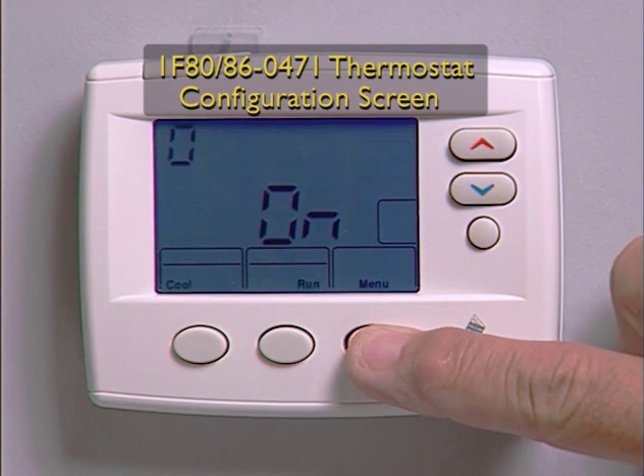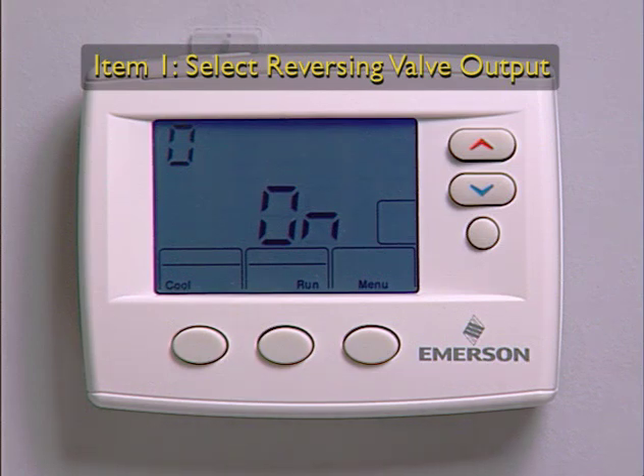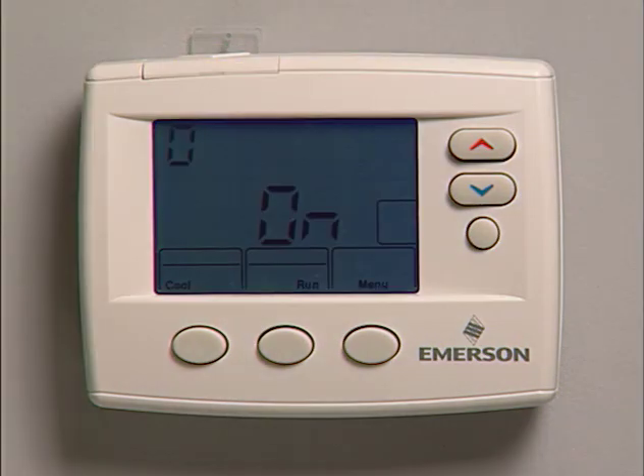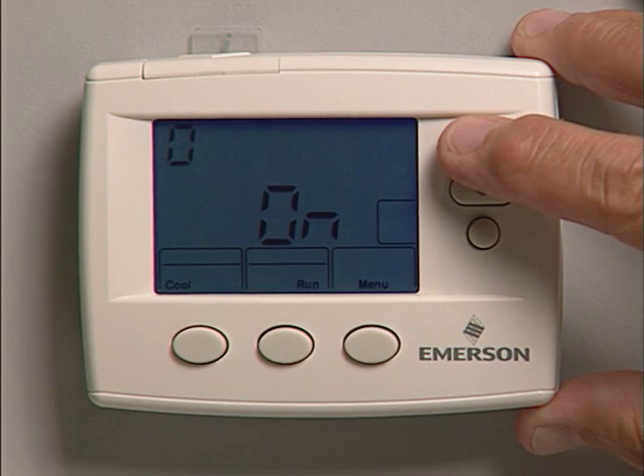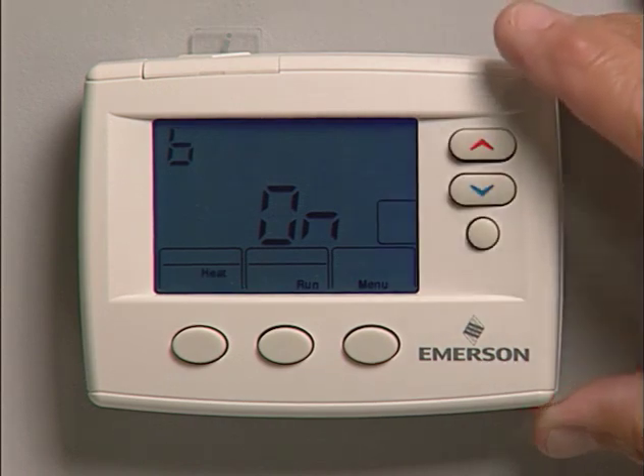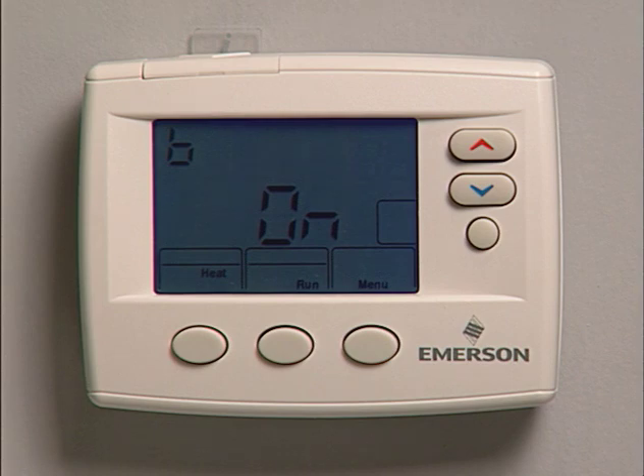When the thermostat is set for heat pump, this brings up the display O-ON. For menu item 1, select reversing valve output. The default option O accommodates most heat pumps requiring the changeover relay to be energized in the cooling mode. If your system requires a B terminal to energize the changeover relay in the heating mode, press the arrow key to select B. Press the run button to exit, or the menu button to continue through the configuration menu.